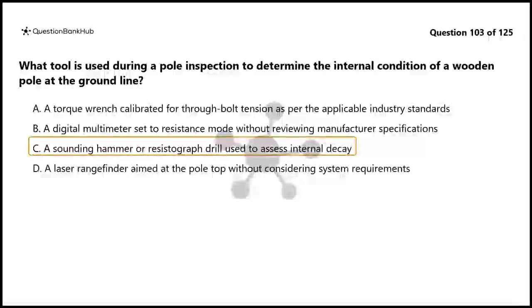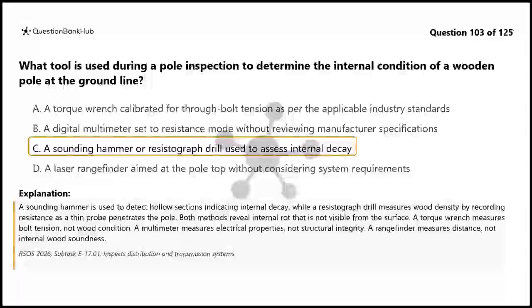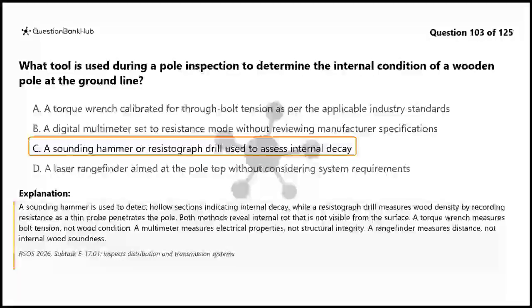The correct answer is C. A sounding hammer is used to detect hollow sections indicating internal decay, while a resistograph drill measures wood density by recording resistance as a thin probe penetrates the pole. Both methods reveal internal rot that is not visible from the surface. A torque wrench measures bolt tension, not wood condition. A multimeter measures electrical properties, not structural integrity. A rangefinder measures distance, not internal wood soundness.